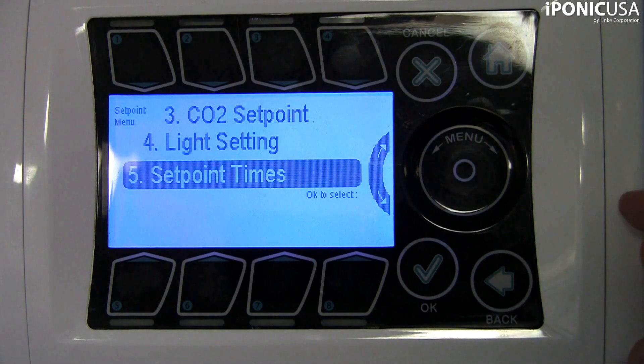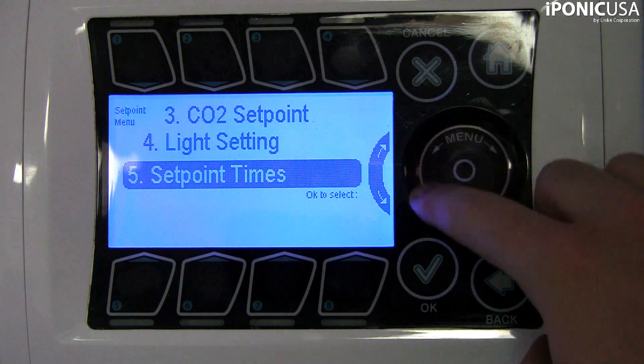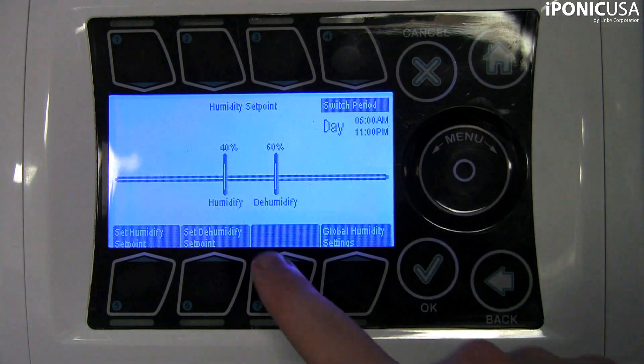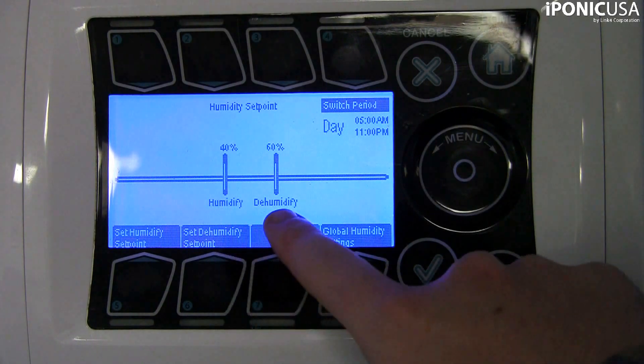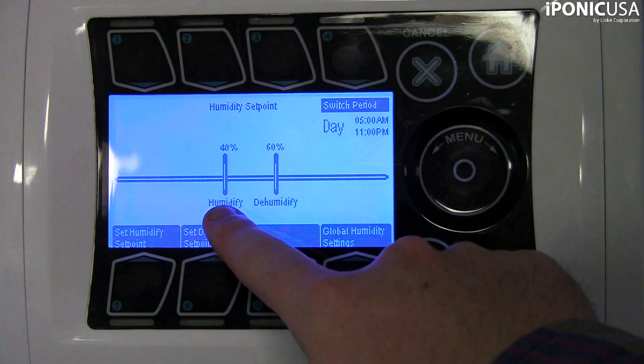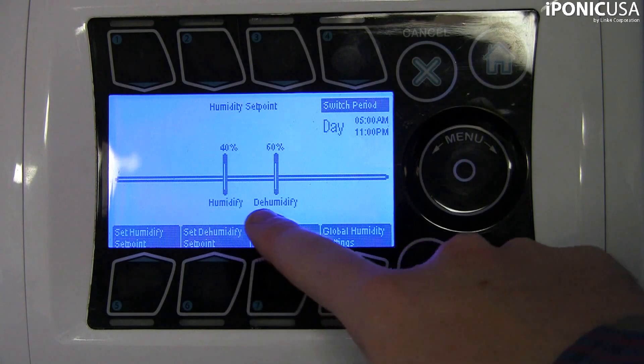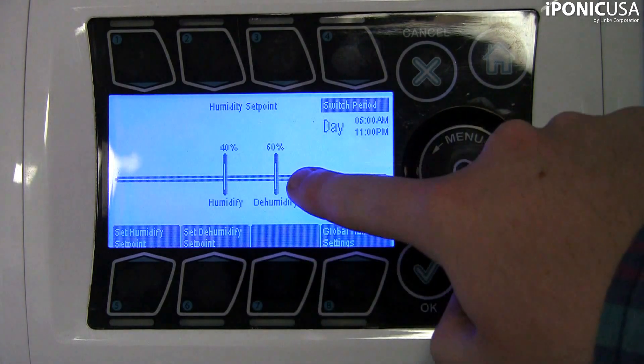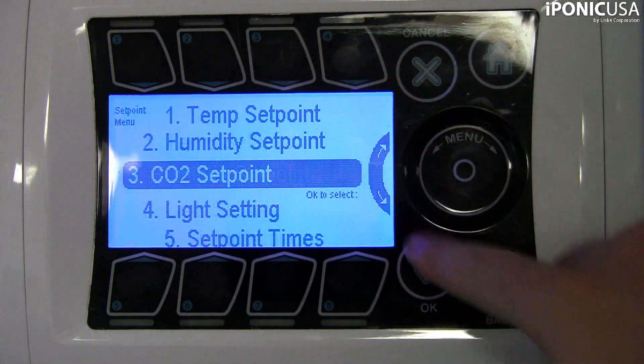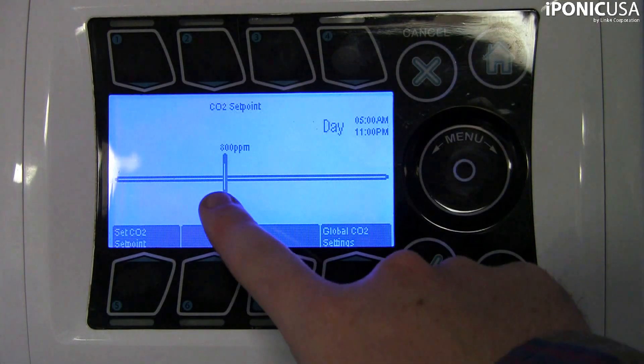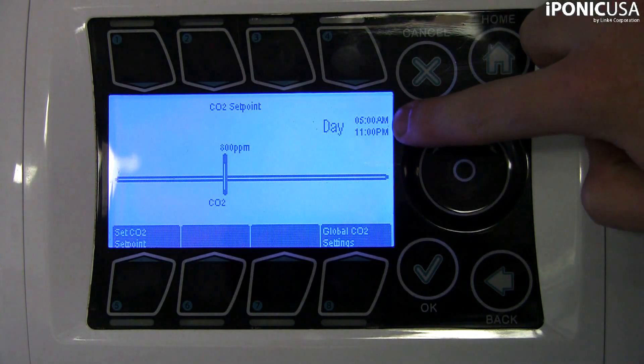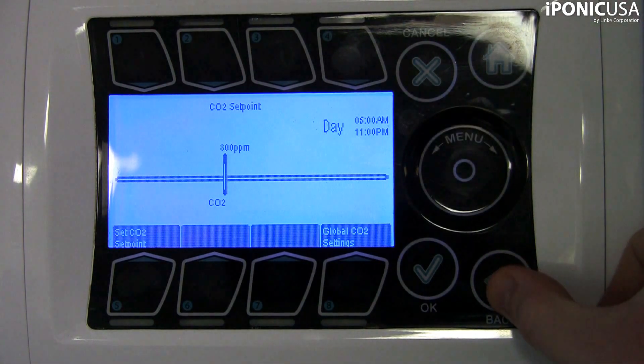A humidify and dehumidify set point can be configured for each time set point, which will activate installed equipment when the humidity falls below the humidify set point or rises above the dehumidify set point. The same applies when the CO2 level falls below the target for that time set point. The time set point will also determine whether any installed lighting equipment is on or off for the duration of the set point.